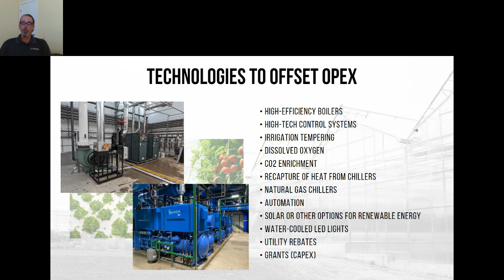We've created this system that goes up against either a gable wall or the outside wall of an indoor warehouse facility. This is not the only option, but it's one of them. So right here you've got the insect screen, this green part is the evaporative cooling pad, this yellow is the free CO2 you're getting, and these are our supply and return pipes going to our air handlers. The blue is the cooling coil, the red is the heating coil.